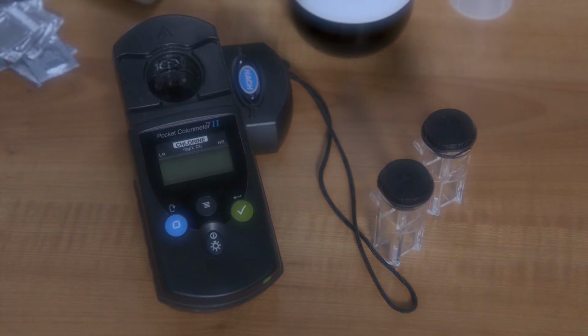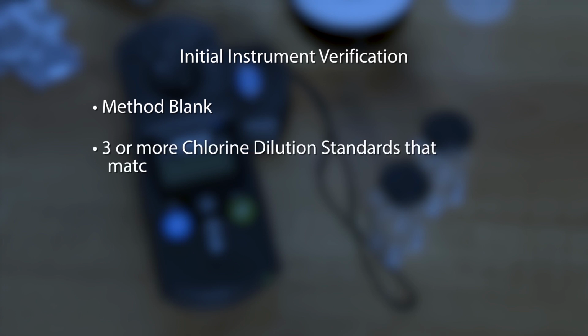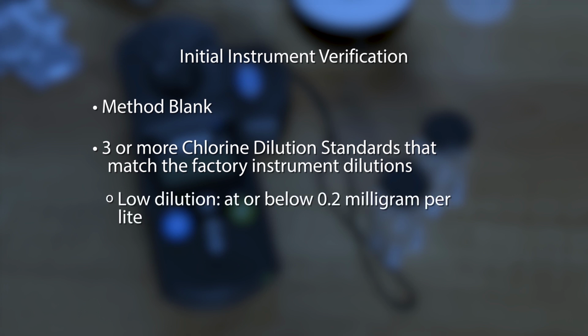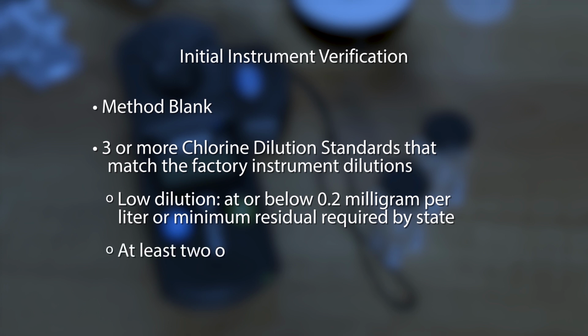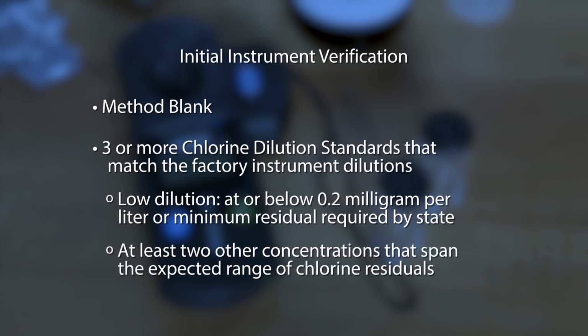If you have purchased a new instrument, you are required to perform an initial instrument verification. The initial instrument verification consists of the following steps: a method blank, at least 3 calibration standard dilutions that match the instrument factory calibration dilutions, low, at or below 0.2 milligrams per liter, or minimum residual required by the state, and at least 2 other concentrations that span the expected range of chlorine residuals.